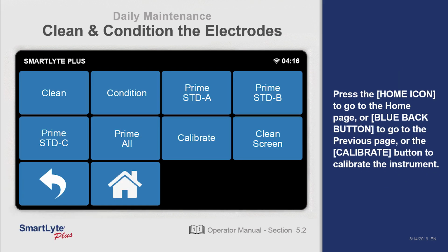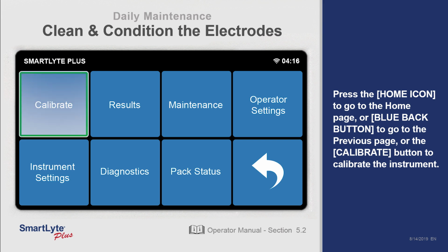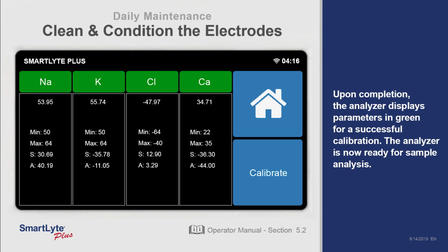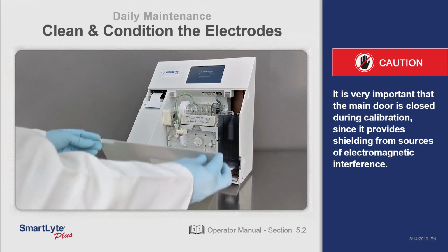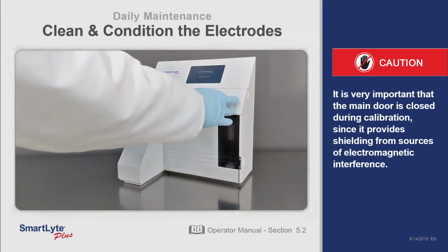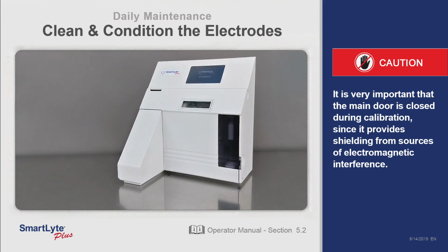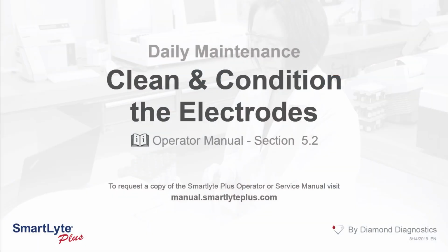When complete, press the Home button or Back button, then calibrate. Upon completion, the analyzer displays parameters in green for a successful calibration. The analyzer is now ready for sample analysis. It is very important that the main door is closed during calibration, since it provides shielding from sources of electromagnetic interference.